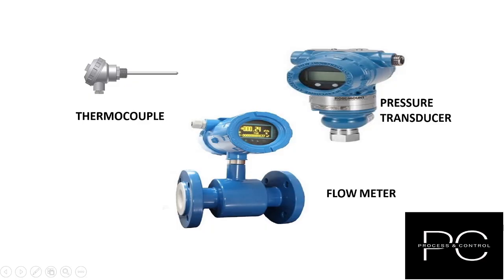Temperature sensors, pressure transmitters, flow meters, etc. are the common analog input devices. The signals coming from these devices are usually measured as 0 to 10 volts, 1 to 5 volts, 0 to 20 milliampere, 4 to 20 milliampere, etc.